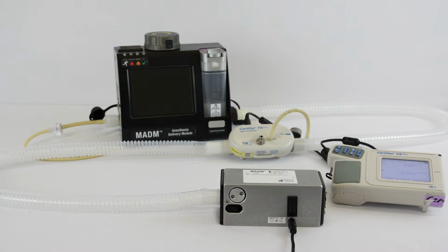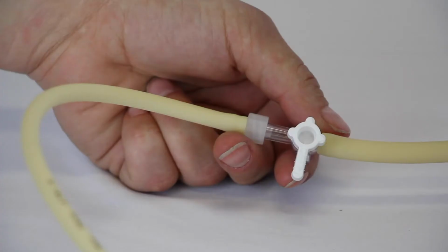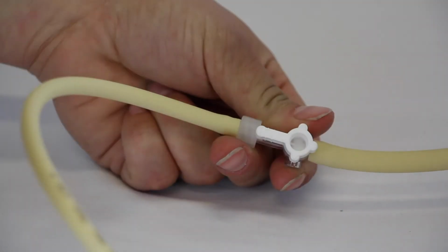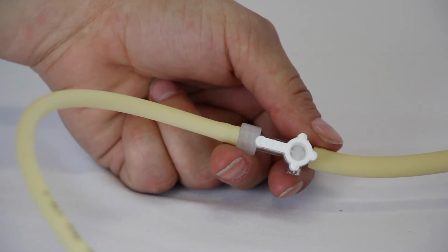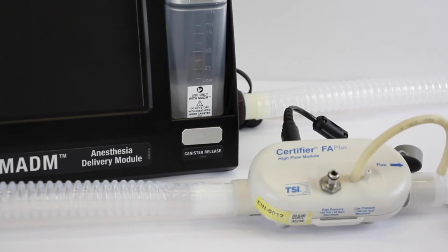If a ventilator analyzer is available, it can be placed in the test setup in place of the flow meter, and the pressure meter will no longer be required. Ensure that the stopcock on the pressure leak test plug with tube is closed before running the test. Then take the flow reading from the ventilator analyzer while also reading pressure.